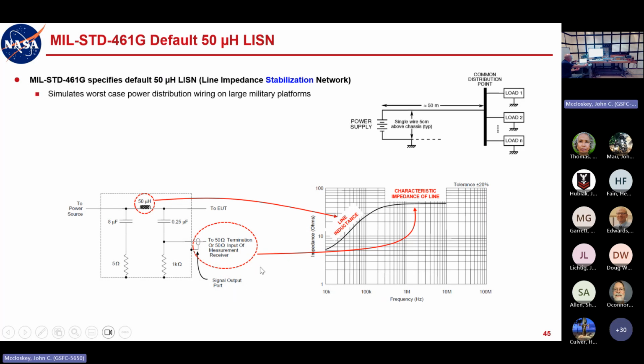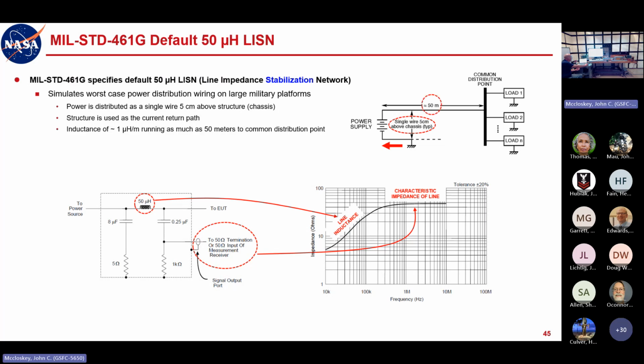This simulates the worst case power distribution wiring on large military platforms, where power is distributed as a single wire 5 centimeters above structure or chassis. Structure is used as the intentional current return path, which we don't tend to do on spacecraft. That configuration gives you an inductance of about a microhenry per meter, running as much as 50 meters to a common distribution point.